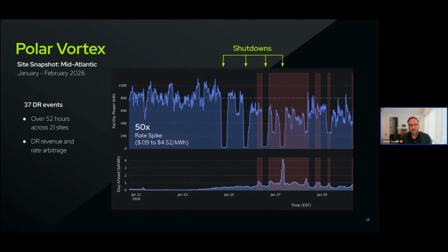And this is the Atlas control system automatically shutting down one of the sites in the Mid-Atlantic. Over the course of this entire storm, across our sites exposed to it in PJM, we had 37 demand response events, which occurred over about 52 different hours across 21 sites in this section of the United States. The total net value to us, which included net savings plus demand response revenue, was about $351,000, and it all occurred within basically what you see here, about a week.